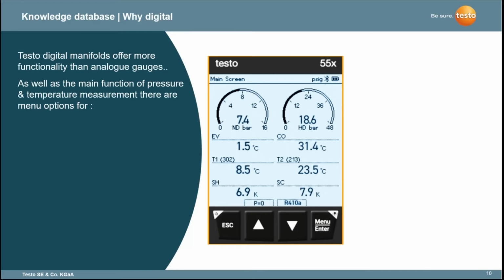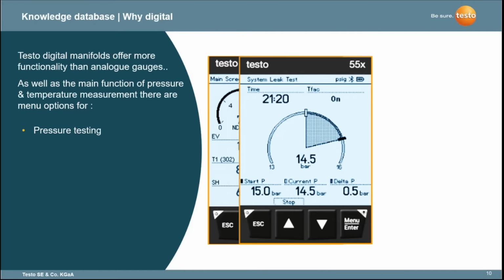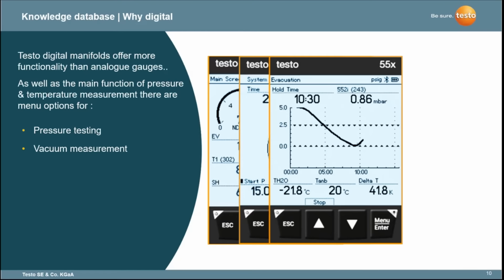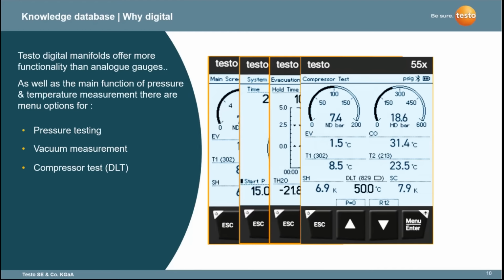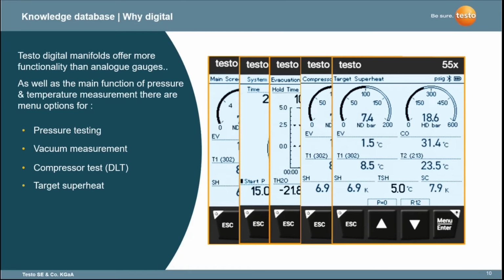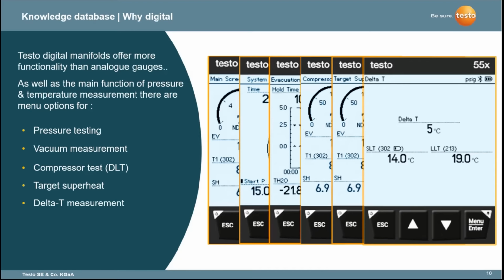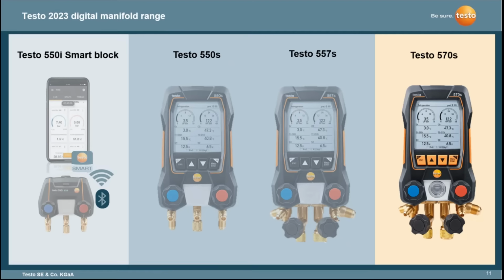And as outlined, the digital manifolds offer much more functionality than just this replacement as an analog gauge. So you get the screen for a traditional replacement for an analog gauge, but there are screens for the pressure test on the system. Evacuation, the screen changes slightly. So rather than having a gauge mimic, you actually have a graph so you can see the decay of the vacuum as it's being pulled down and then stabilizing. There's a compressor test function where you've got discharge line temperature as an extra temperature measurement, and target superheat, and you could even use the device just as a basic replacement for a differential thermometer with two temperature probes and a delta value. So within the device, you have a menu structure where you can easily access all these different tests within the one device. So there we've outlined some of the real benefits of going to digital generally.